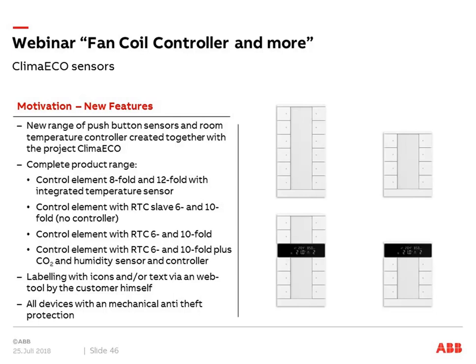It's a really complete range. Starting with 8 and 12-fold push button sensors with integrated temperature sensor. All devices in the ClimaECO sensor range have an integrated temperature sensor. Together with the controller in the FCCS, you can measure temperature, send it to the FCCS controller, and change the set point by pressing buttons — two fixed set points or up/down, or different operating modes like standby and comfort described via the labeling field. This allows operation of a room temperature controller — though with no display for actual values, it may be sufficient in some cases.